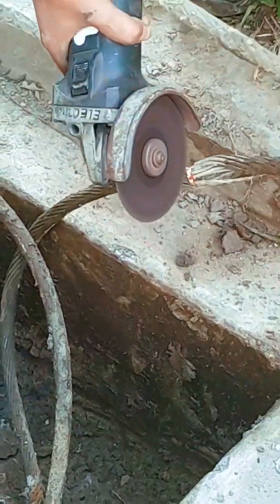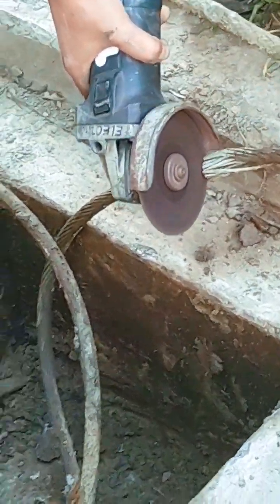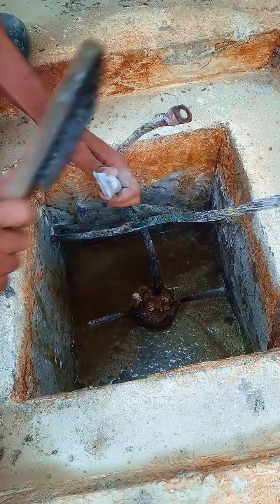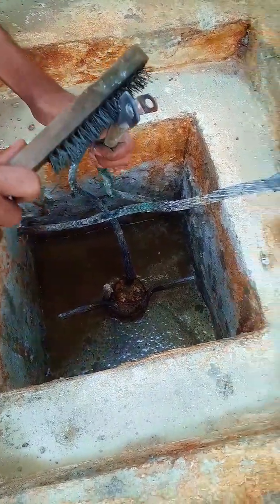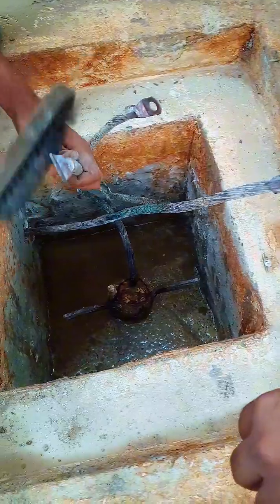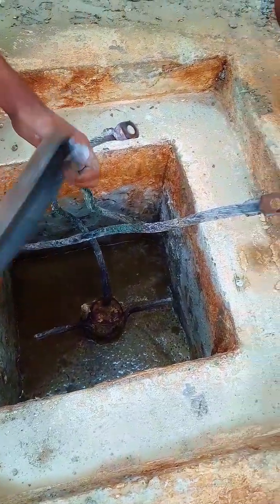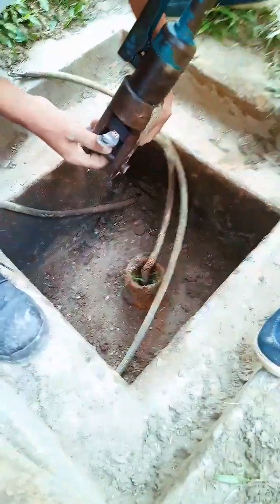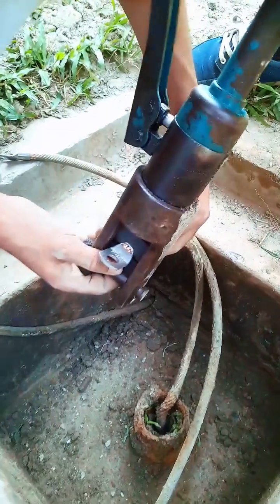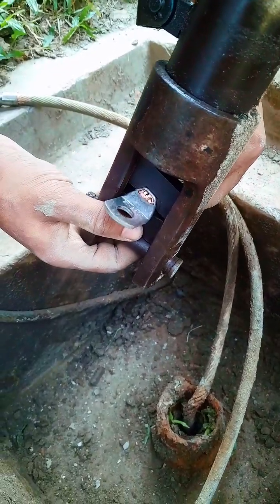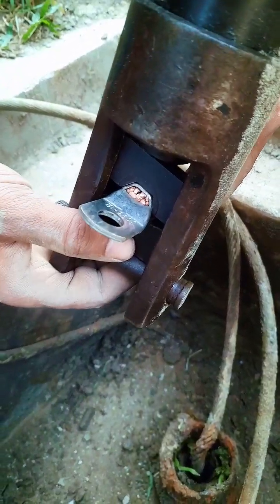Rust on copper increases resistance, reduces conductivity, and can fail when high surge current flows. In many industrial failures, the earthing resistance may look okay, but mechanical degradation silently weakens the system. And that is even more dangerous, because you trust a system that cannot protect you.